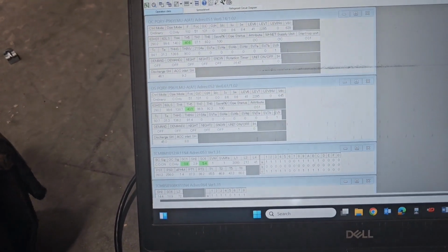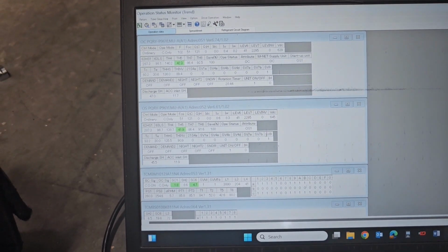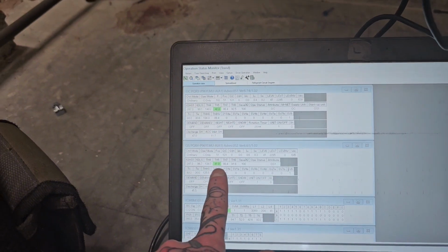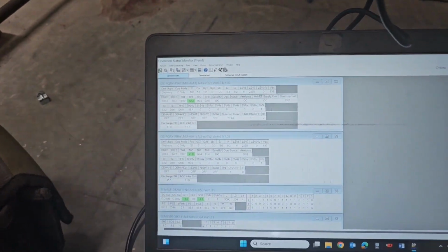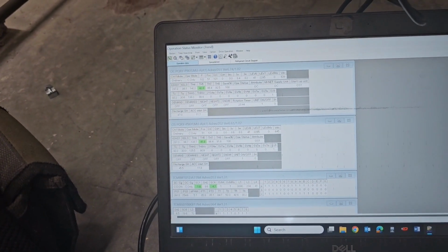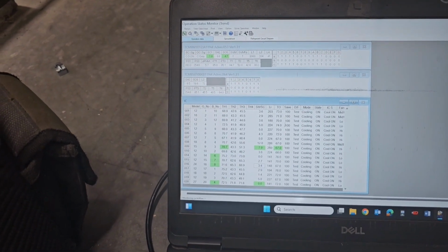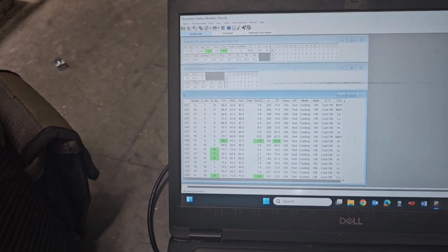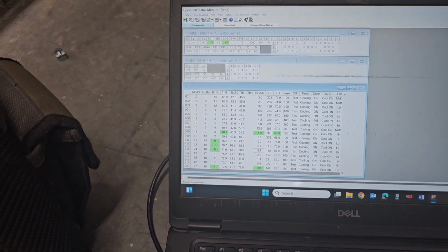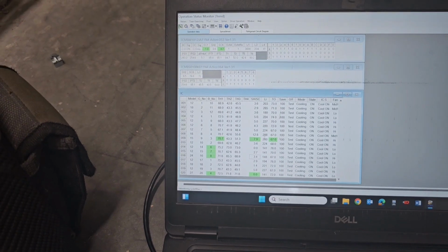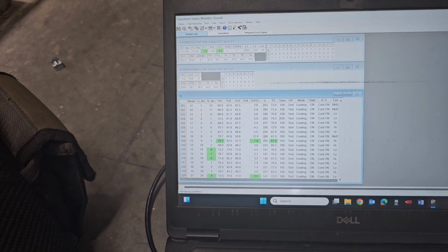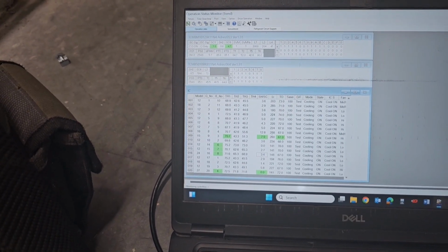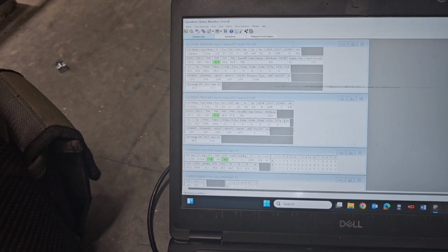But earlier, if I go back 15 minutes or so, as soon as I closed those ports on the BC, I immediately saw more superheat at my outdoor unit. So like I said, this is still under investigation, but I'm really leaning towards having several failed LEVs that are stuck in the open position. Unfortunately, that's going to be quite a pain, but that's what everything is pointing me towards now.